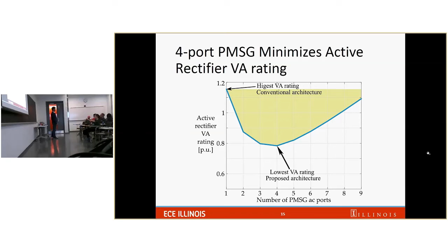When we look into the power processed by the active rectifier, we see that if we only have one AC port, this is how much power needs to be processed by the active rectifier. If we have 4 AC ports, because a portion of power is supported by the passive side, the active rectifier only needs to support a portion of the power. By reducing the amount of power processed by the active rectifier, we actually gain efficiency. So this goes directly to your answer.